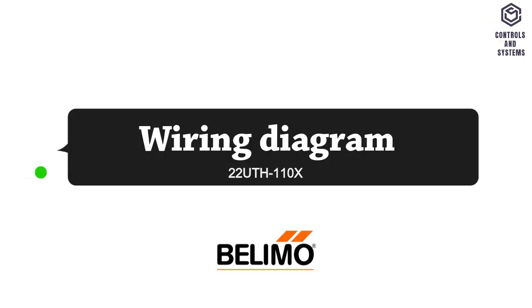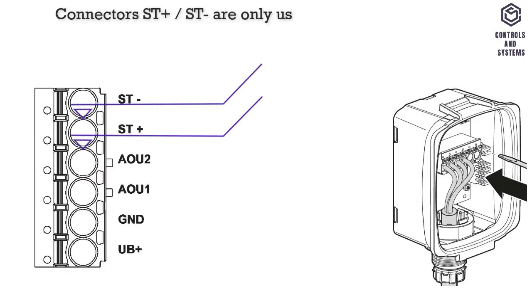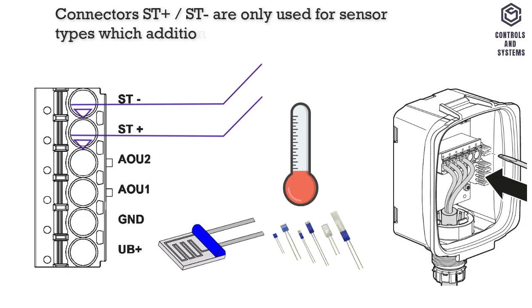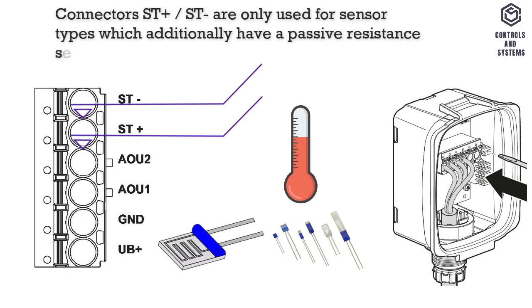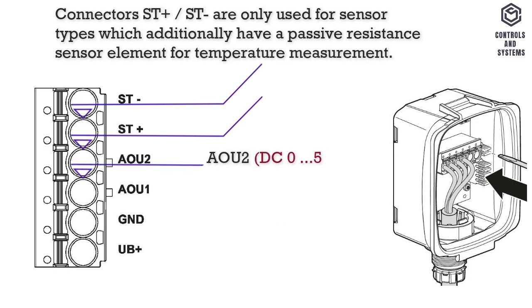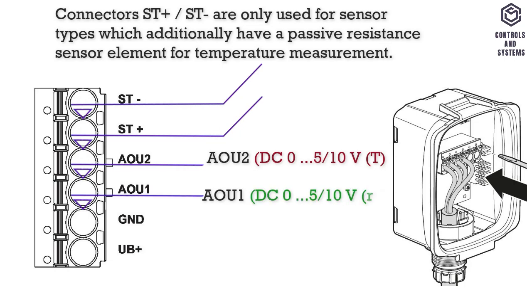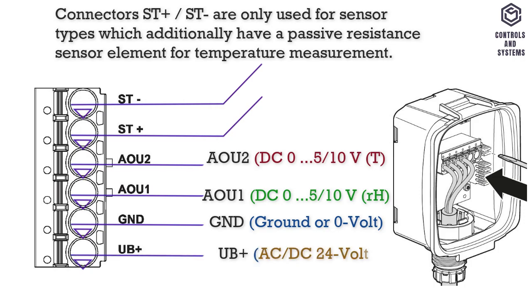Wiring diagram. Terminal ST plus and ST minus are only used for sensor types which additionally have a passive resistance sensor element for temperature measurement. Terminal AOU2 means temperature output. Terminal AOU1 means relative humidity. Terminal GND means 0 volt. Terminal UB plus means 24 volt.